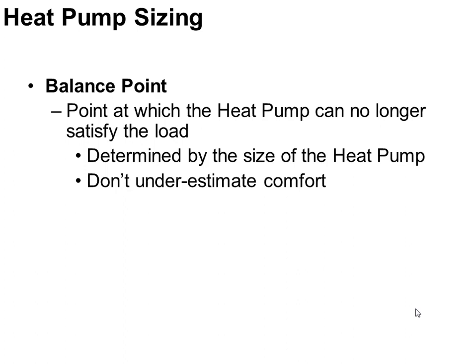So when we're picking one of these heat pumps, we've got to figure out at design time when the heat pump's going to have to shut off and when we're going to have to turn on another heating source, right? So we look at what's called a balance point. There's two types of balance points. There's a thermal balance point, which is what outdoor air temperature can my heat pump no longer make enough BTUs to heat my house. And then there's the economic balance point, which is based on how cheap gas is or how expensive it is versus electric. At what economic point should I go ahead and shut this off and turn on my gas furnace, right? So we need to find both those numbers, and one of those two numbers is going to dictate when we decide to change the heat pump over to gas furnace operation.